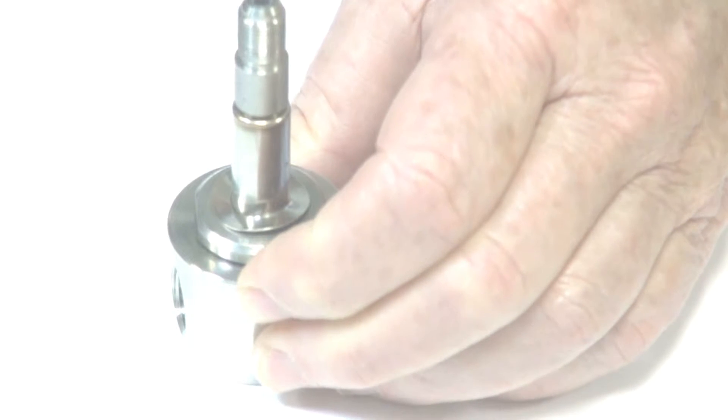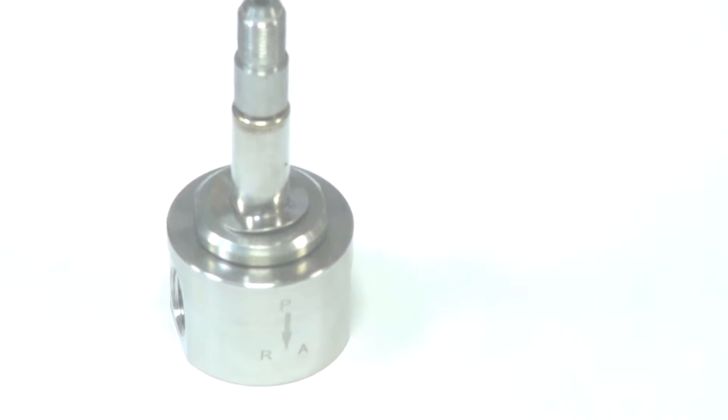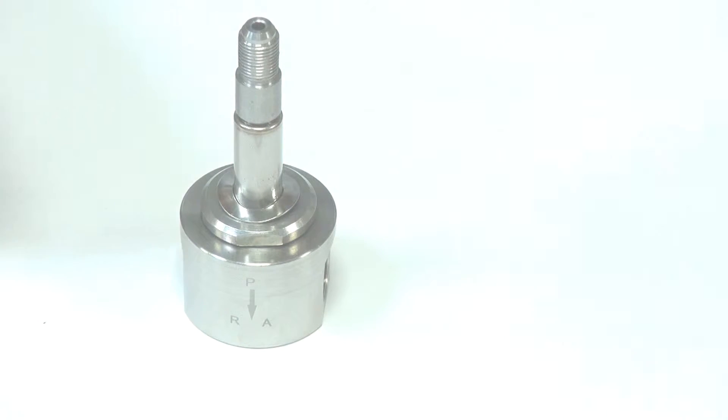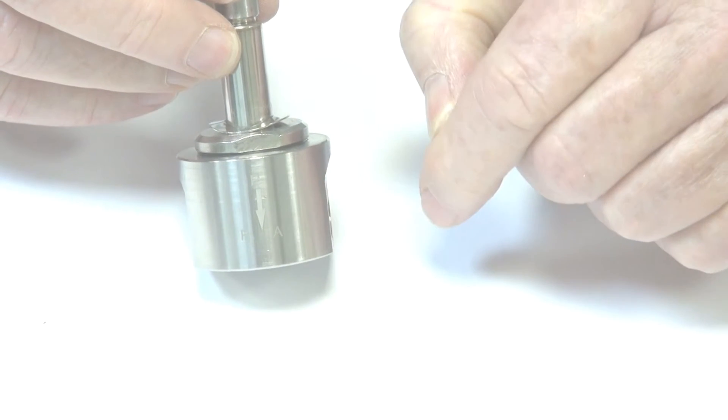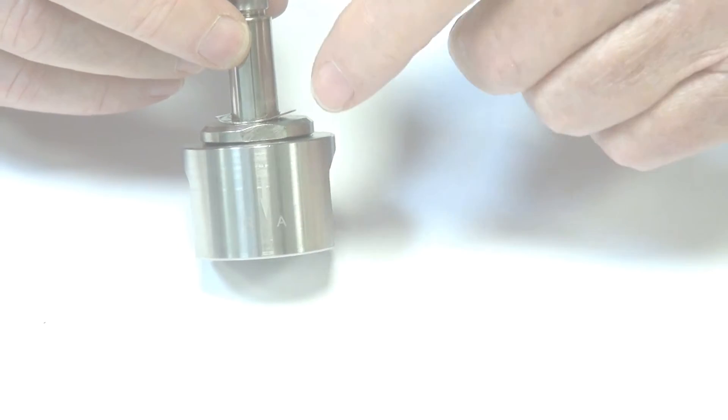The coil slides off like that, so it can be serviced in situ. This is a three-way normally open valve, so when the supply is connected on the top here, it's feeding through and out through port A.